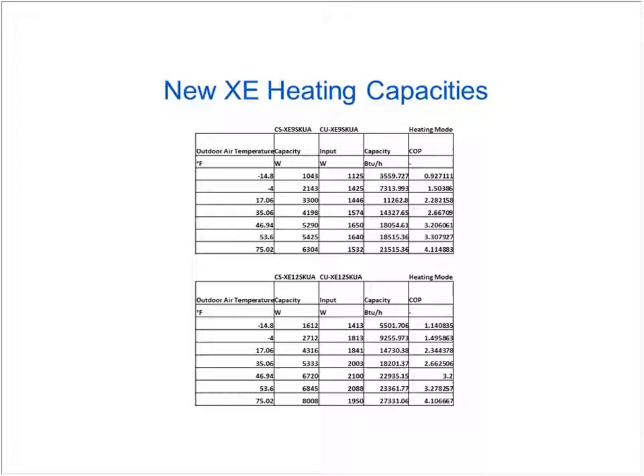So while all of the manufacturers, or not all of them, I shouldn't say, can go to a minus 4 anymore. And minus 14.8 or minus 15 is a big stretch, but your output is going to be diminished, and quite frankly, you'd have to check your individual COP values, but most likely you're better off with electric heat at that temperature. So that's kind of the fuzzy part of COPs. You can see it's a sliding scale.